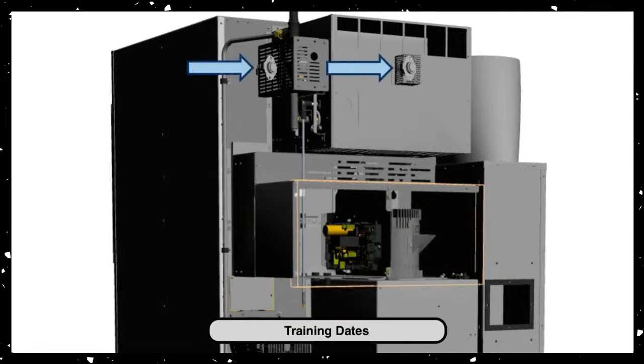Two thermostats on your stack tumbler are located on the burner assembly, or stove assembly. Those two thermostats up top are called stove limit thermostats. They face the flame or heat inside the stove, so that if we ever had poor airflow and air wasn't being drawn through the stove like it should, these thermostats are our savior. They should keep it from getting too hot, they'll open up, the gas valve will lose power, and we won't keep heating because it's not a safe environment.